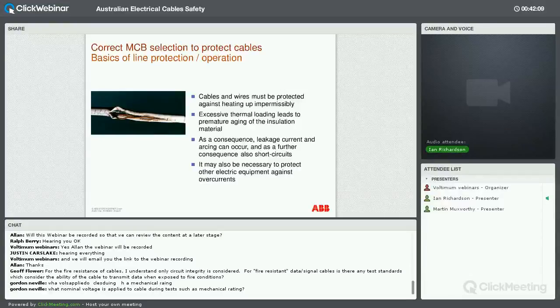Even a small increase in the thermal loading or the operating temperature of the cable can lead to a premature aging in the insulation, and we get breakdowns occurring of the cable itself. So it's actually quite important that we give good consideration to the selection of our protective device, in particular around the thermal aspects of the protective device, so that we are offering the correct protection.